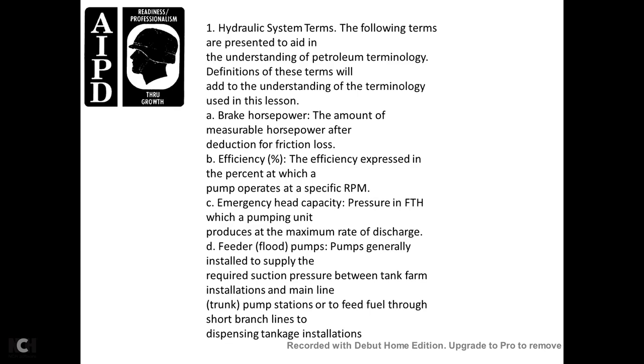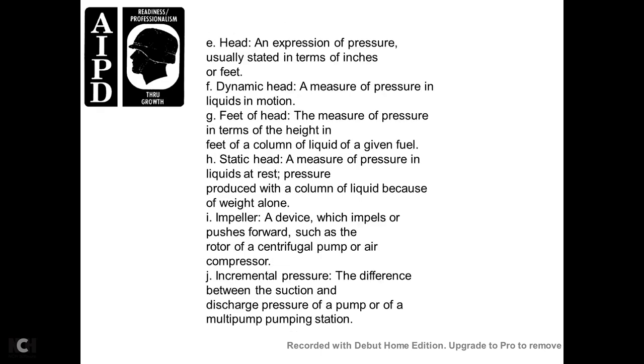Flooded pumps are pumps generally installed where the supply provides the required suction pressure, such as in tank farm installations, mainline trunk pump stations, and short branch line dispensing tank installations. Head is an expression of pressure usually stated in terms of inches or feet. Dynamic head is a measure of pressure of liquid in motion, measured in feet. Head is the measure of pressure in terms of the height of a column of liquid of a given fuel.